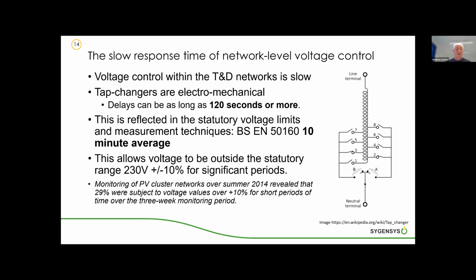the GB grid. So we may think of our 230 volts plus 10% minus 6% as what voltage we'll see for a typical consumer. That specification is actually based on a 10-minute average, and it is possible to end up with excursions beyond that for quite significant periods of time.